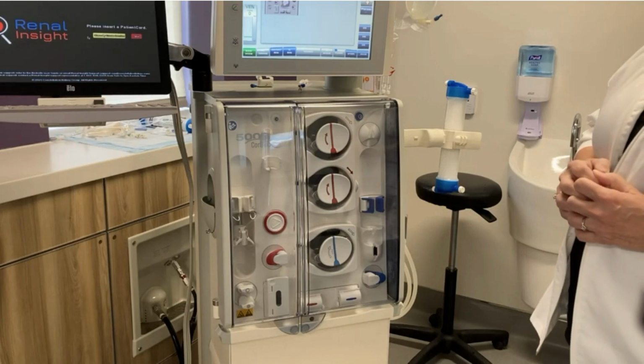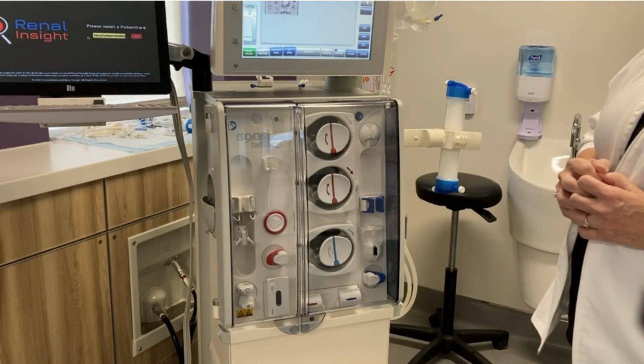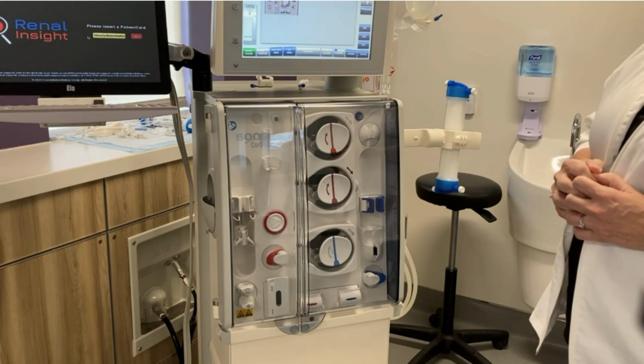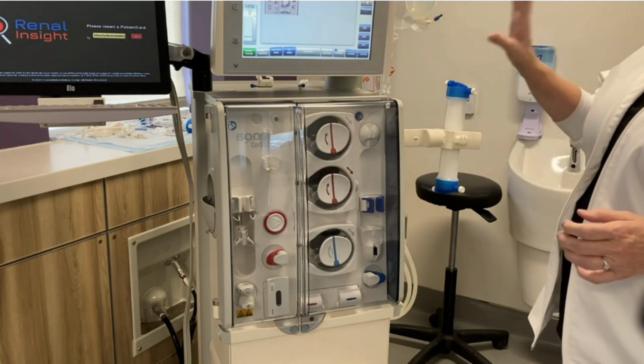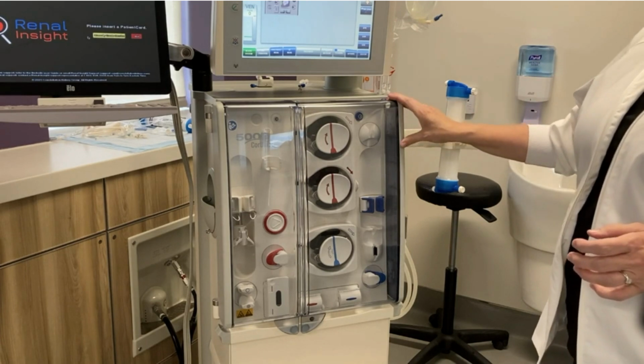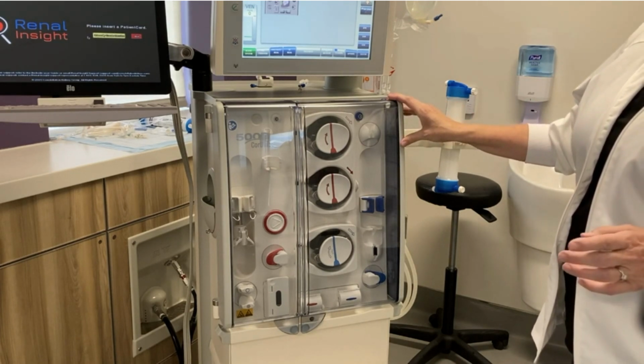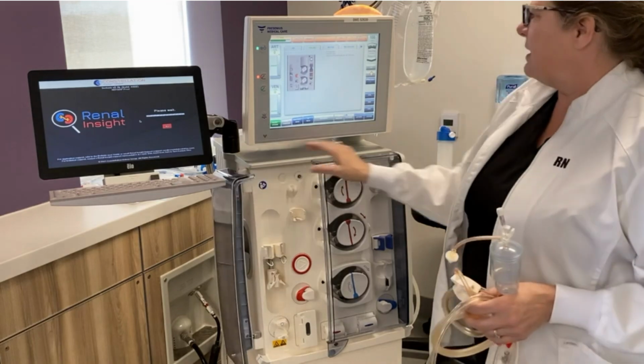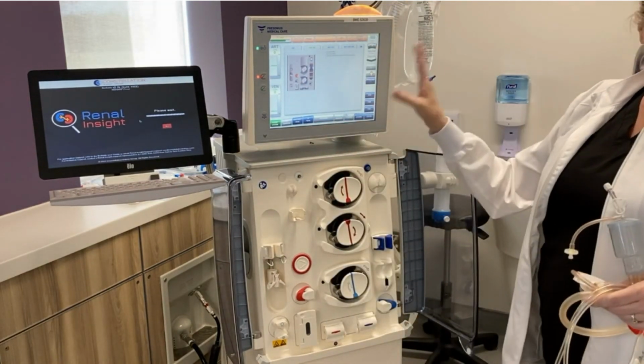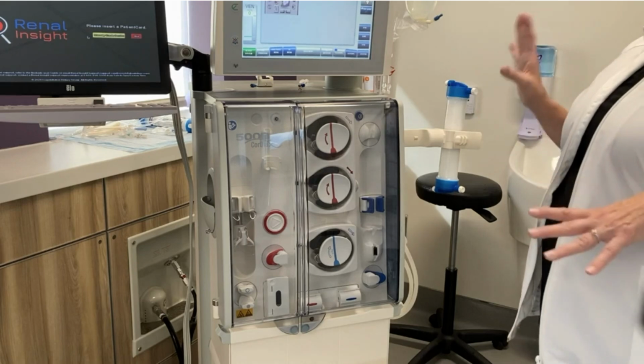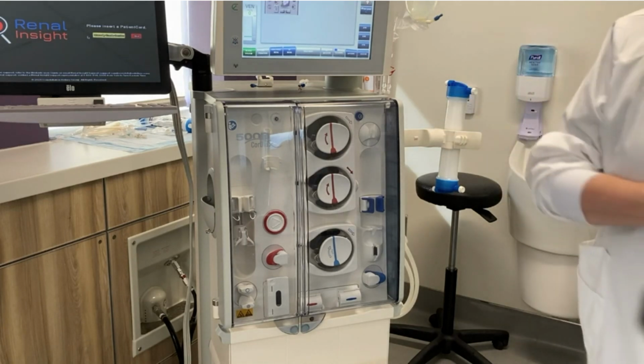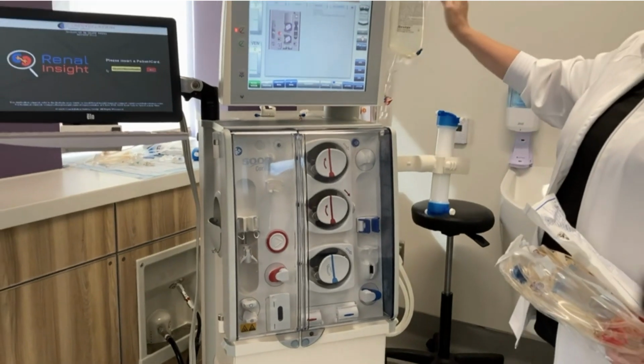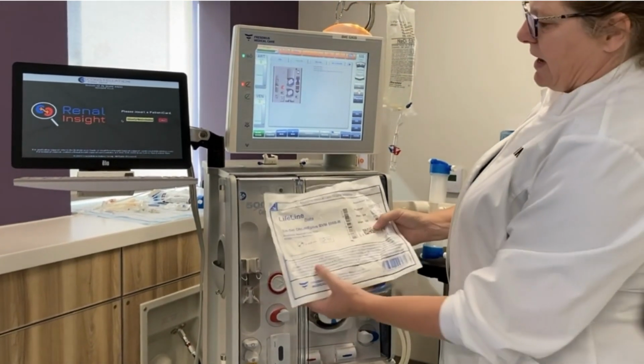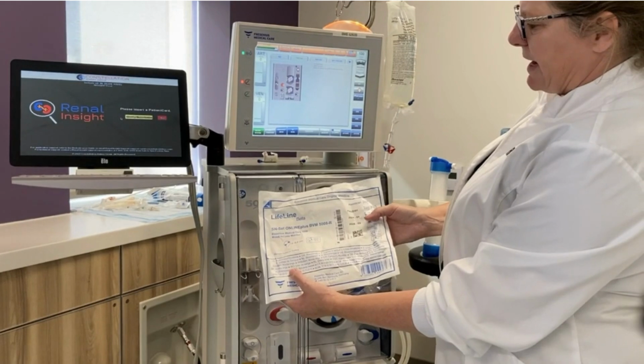So we're talking about setting up for single needle dialysis on a double pump machine. This specific machine allows us to do single needle dialysis because it has two pumps. We start dialysis, our T1 test, just as per normal. So we have all the same supplies as a regular setup. I've got my saline ready, my drain bag, and I've got a single needle set here.